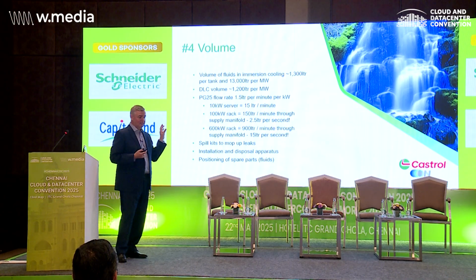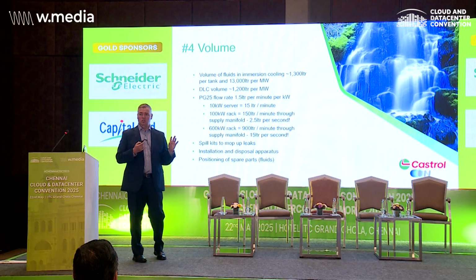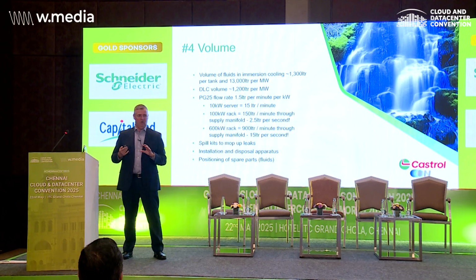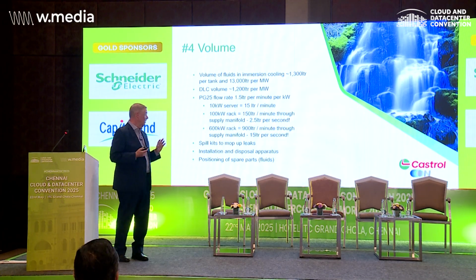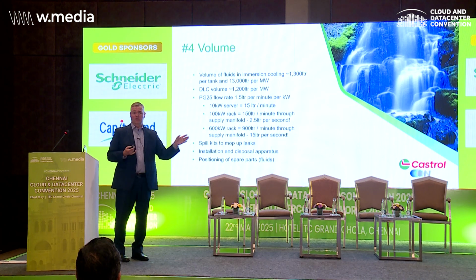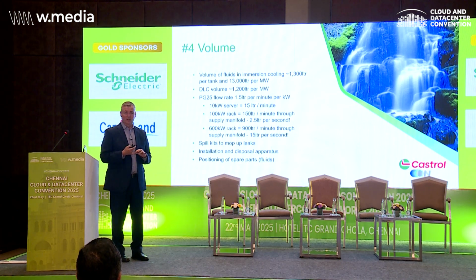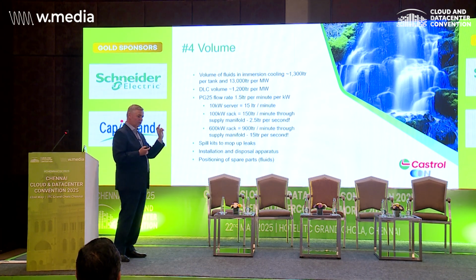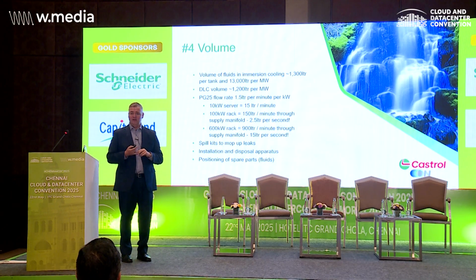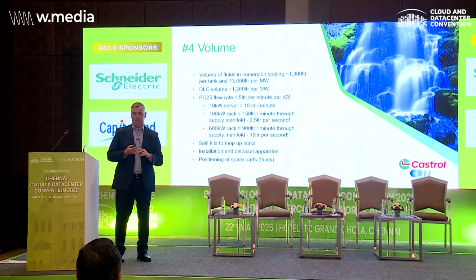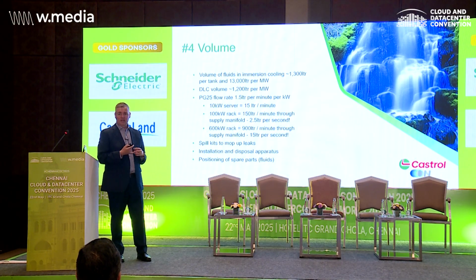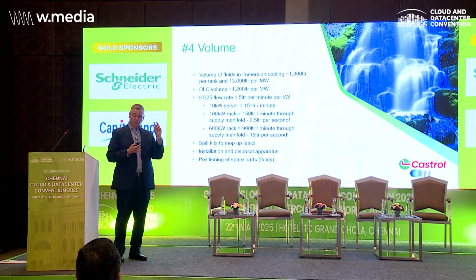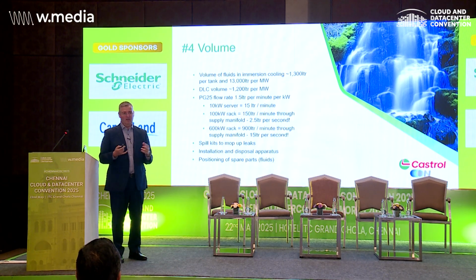Whilst DLC technology doesn't use as much fluid, the flow rate here is quite interesting to understand. There's a rough rule of thumb, for any consultants in the room I'm sure they'll concur, that it's 1.5 liters per minute per kilowatt. So when we step that through, a 10 kilowatt rack or server is 15 liters, not that much.